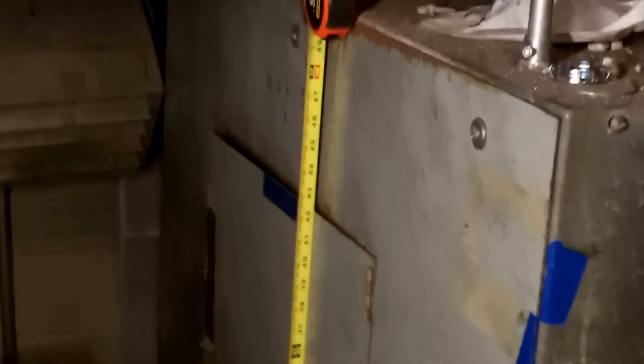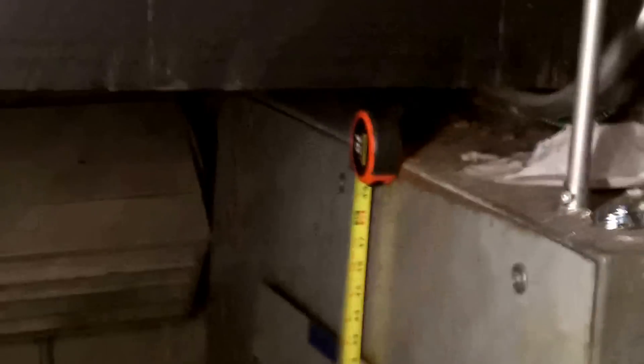So it's going to be impossible for somebody to stand in front of this panel board and work safely. You'd have to be crouched down, possibly kneeling down. That's going to create an unsafe situation. This headroom is very, very small here.